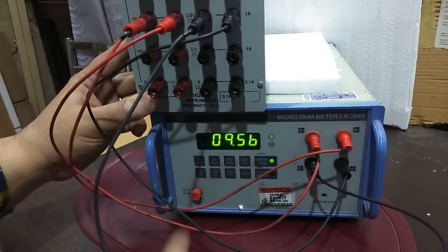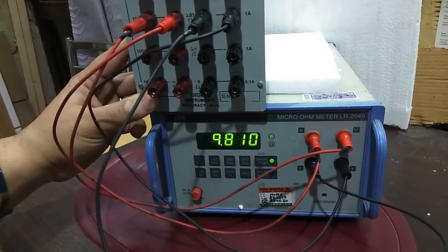Now it's ten milliohm. Ten milliohm is also good. The results are fine and within the accuracy of the standard resistance box as well as this instrument.